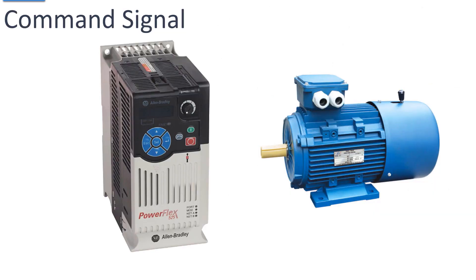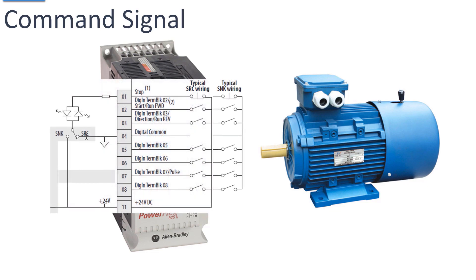Another digital output from a PLC is a command signal. Instead of using a motor starter, you might use a variable frequency drive, which you can use to control the speed of an AC motor. Here's a typical example of some connections on that drive — terminals one through eight are digital inputs, four is a common, and digital inputs five through eight can be programmed to be whatever you want. The PLC would send signals, closing contacts and feeding 24 volts DC to these terminals to control the drive.